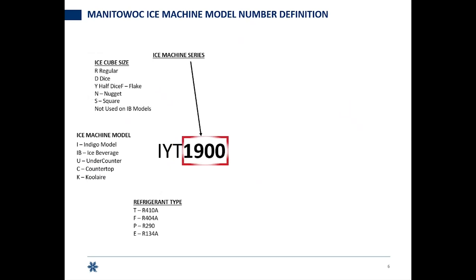After that, we're going to call out the ice machine series. This one's called out by 1900, and that's letting you know that this machine, in the best conditions — with 70-degree air entering the condenser and 50-degree water entering the water trough — in 24 hours could make about 1,900 pounds. Change the air or the water or have safety shutdowns or full bins, and that number is going to change.